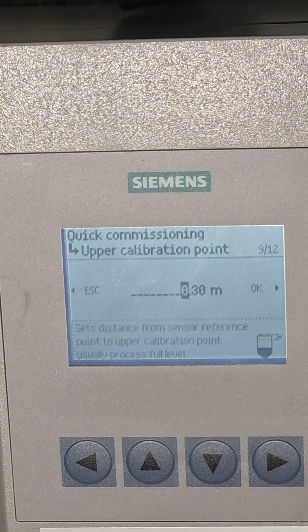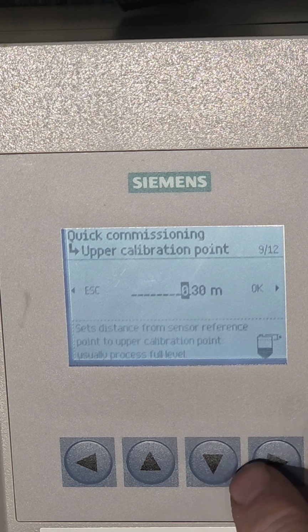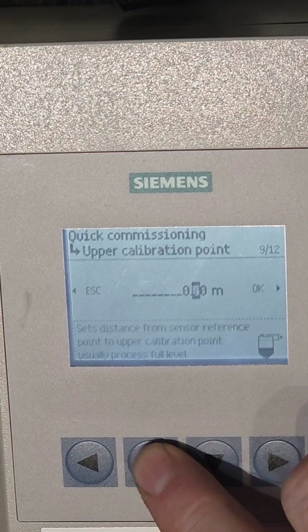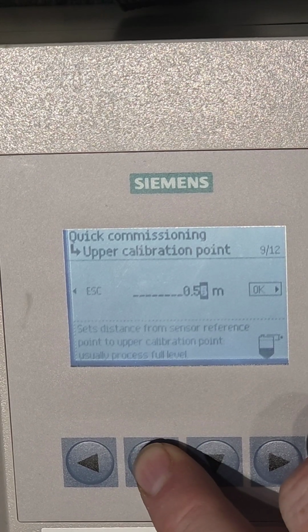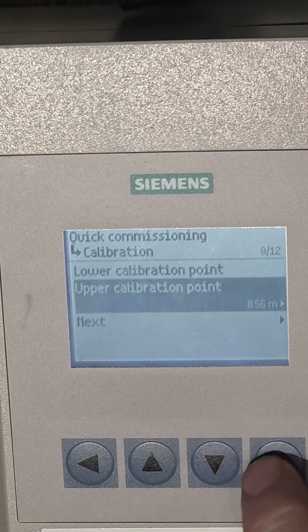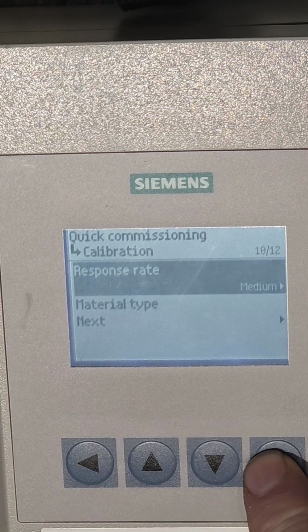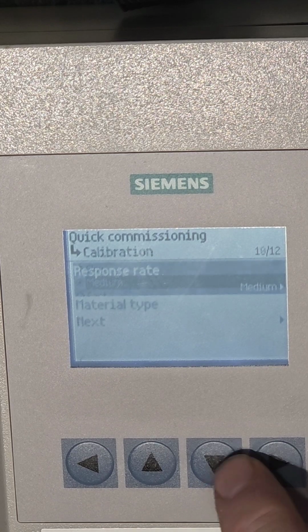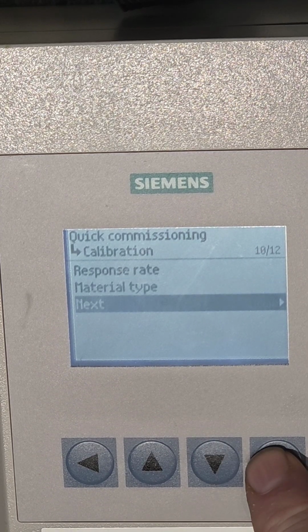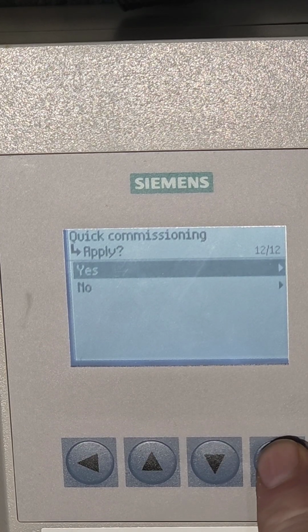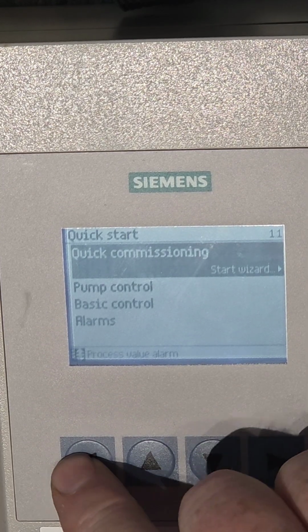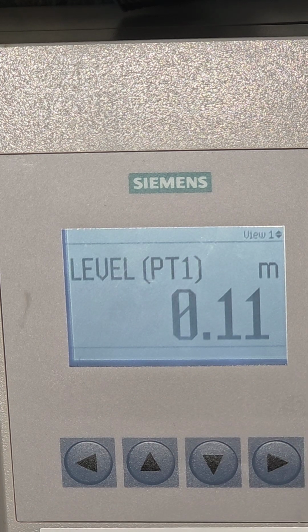The upper calibration point is the empty distance minus the span. So my span is 1.2 meters, and we take that away from 1.76, the empty distance, and that gives you 0.56. 0.56, right click, OK, down to next. Response rate is medium. Material type is liquid, down to next, right click. Do you want to apply these changes? Yes. And we come back out to the front view, and that's reading now correctly.